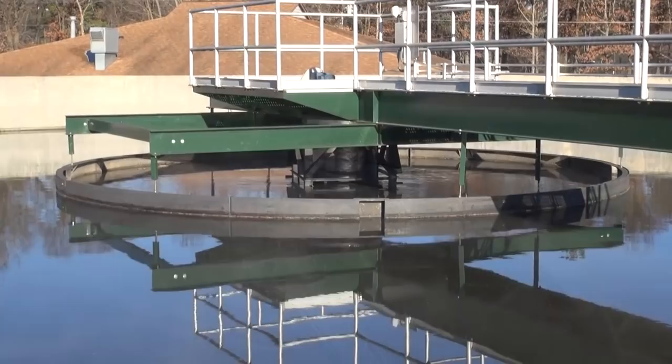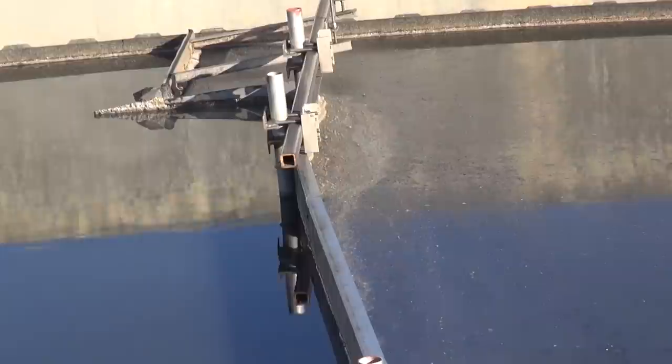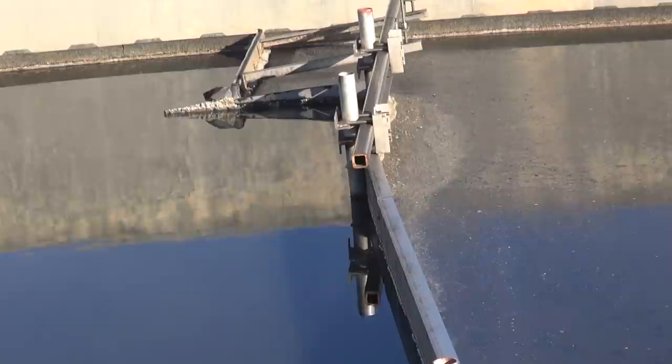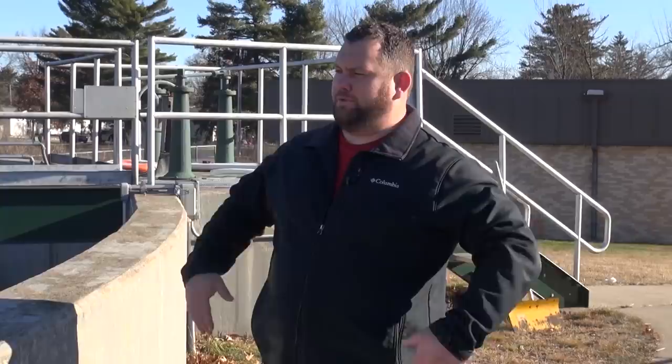You can see out in the middle how the water's flowing into the tank at that stilling well. You're just allowing gravity to pull out the heavy solids — removing about 30 percent of your TSS, which is total suspended solids, and your BOD, which is the strength of wastewater carbon. It's a pretty rudimentary treatment system in the primary clarifier, but an important step to reduce volatile organic solids and a portion of your soluble BOD to lighten the load on the rest of your treatment works downstream.